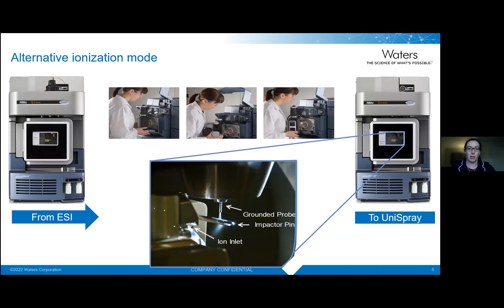How Unispray works is it's a little bit between electrospray ionization and APCI, or atmospheric pressure chemical ionization. Instead of having a charged capillary that the flow is coming through, we leave that probe, or the capillary probe where the liquid's introduced, grounded, and instead apply our voltage to a target pin. It's a stainless steel pin, shown here in the diagram.